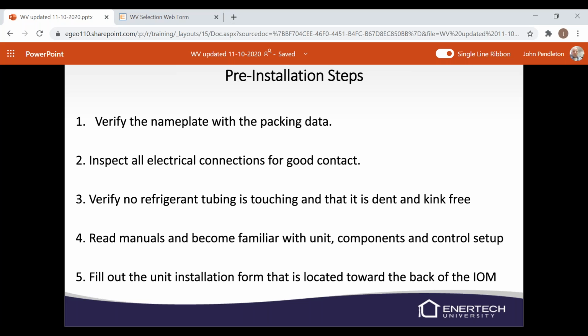Once you have installed the unit, we would recommend you fill out the installation form that's located in the back of the IOM. And I would recommend that you make a copy of it and put it in your job folder at your office. And then also you may want to leave one at the unit. That way, if you've got maybe a technician that doesn't know quite as much about geothermal or WV in general, if they go out there to work on the unit, they can pull that out and take a look at it and see how the unit was running on startup and maybe compare, and it'll help them diagnose the unit. But always fill out the startup form in the IOM.